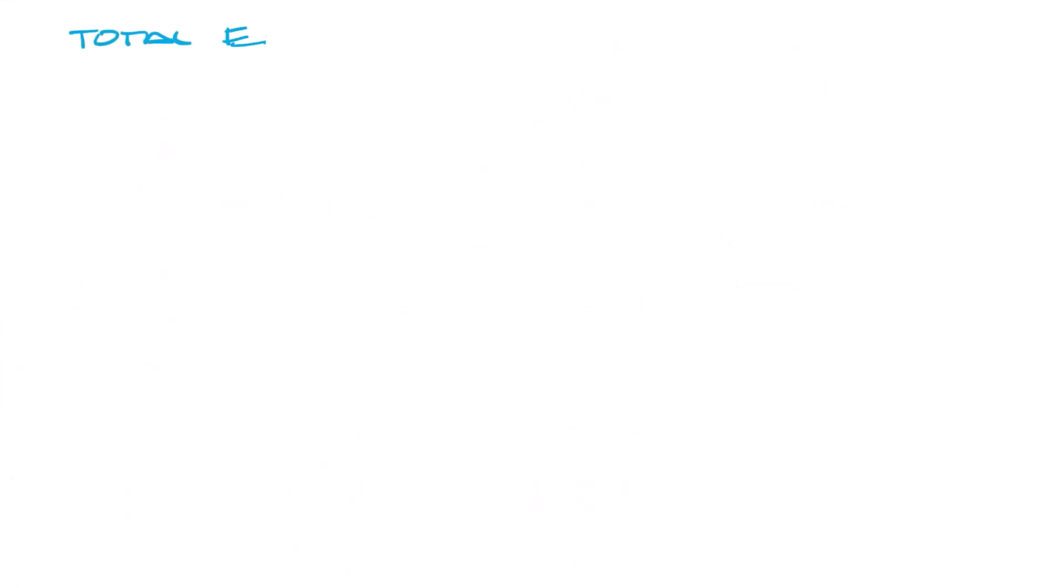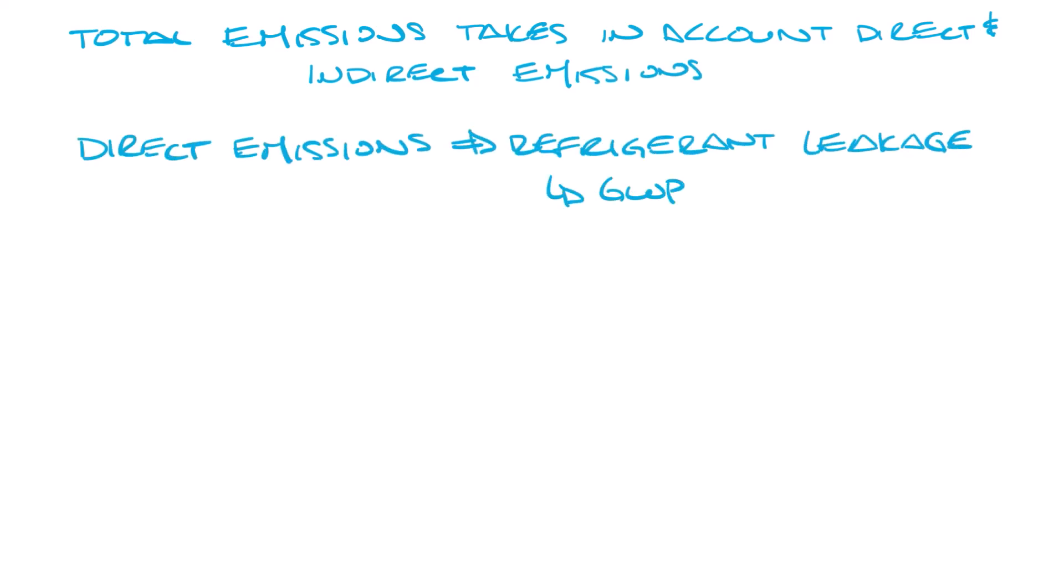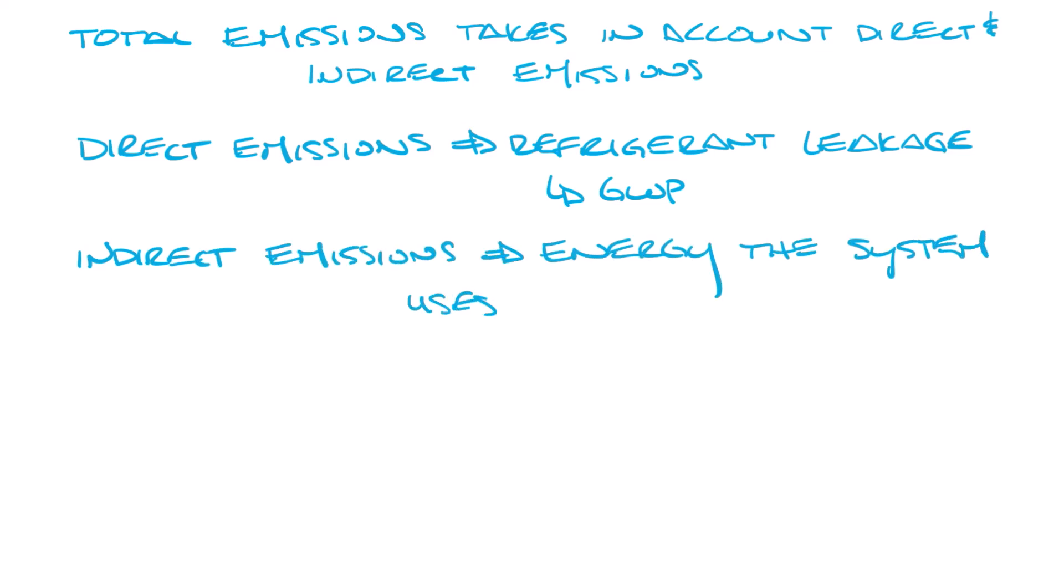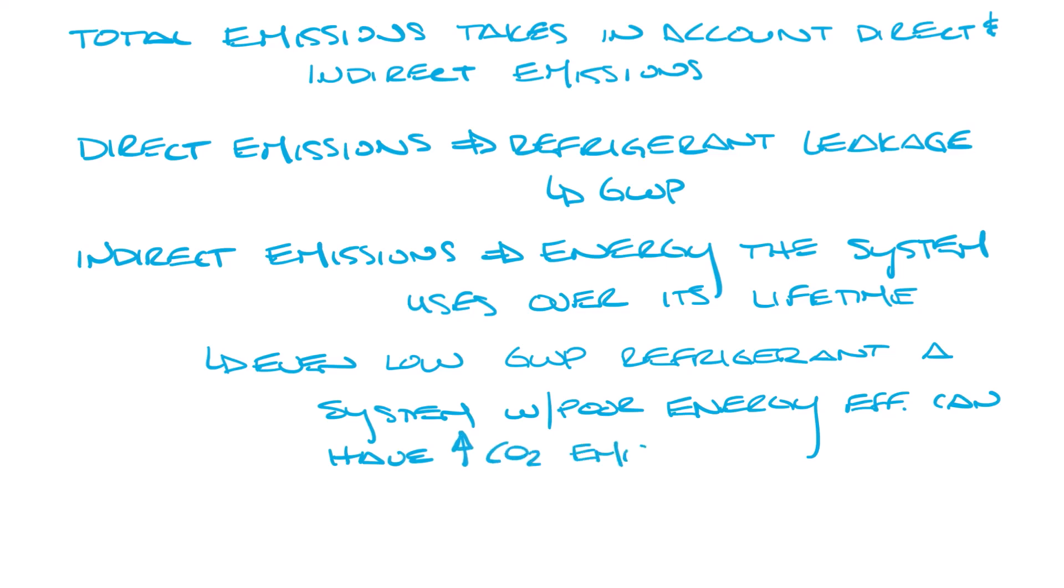Total emissions takes into account both direct and indirect emissions. Direct emissions come from refrigerant leakage, which is where GWP would come in. Indirect emissions come from the energy the system uses over its life cycle. Even with a low GWP refrigerant, a system with poor energy efficiency can have significant CO2 emissions from its daily operations.